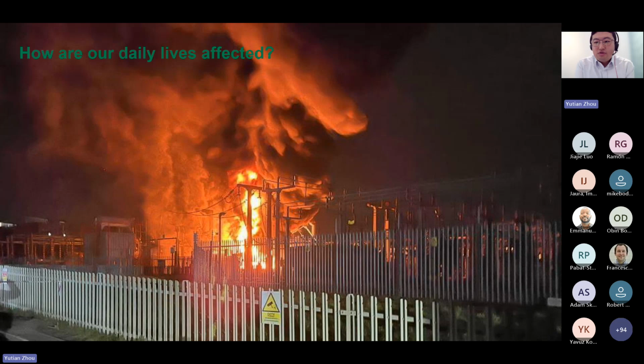And now we come to 2025. On Thursday, 20th March, just 14 minutes before midnight, one of the 3 supergrid transformers at North Hyde substation caught on fire, and its associated circuit connecting it to the wider transmission system tripped. And shortly after that, the adjacent transformers also tripped, resulting in simultaneous loss of connection to the remaining transformer.